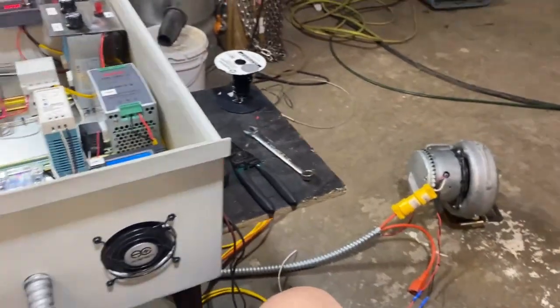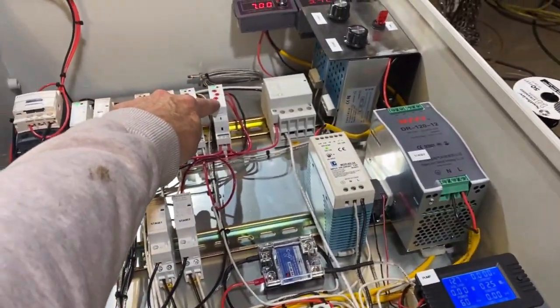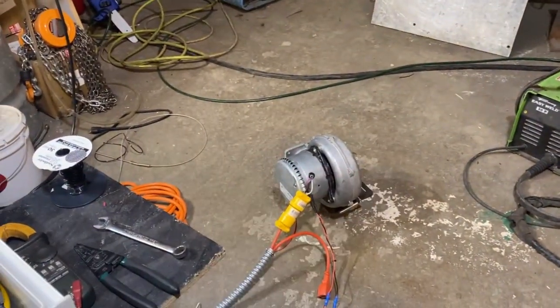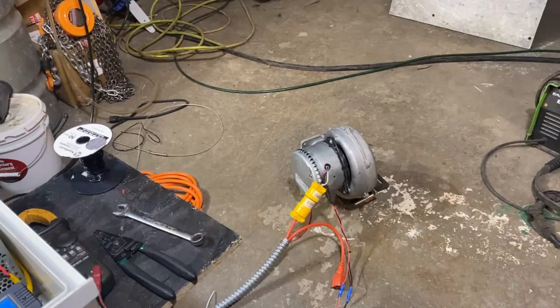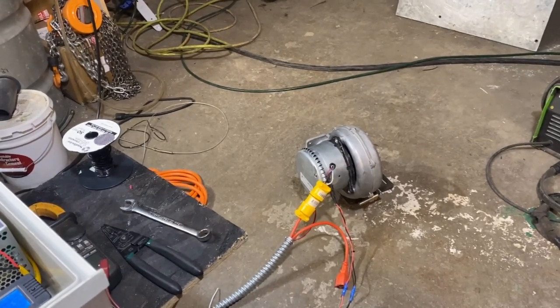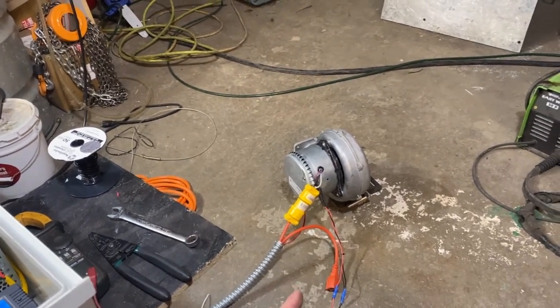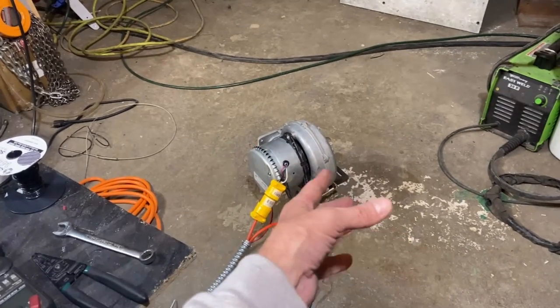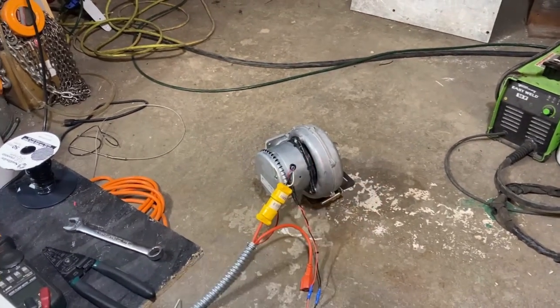So let's take a look, and then once that happens when I go to turn this off we're going to want to see this blower timer relay kick on and run the blower on shutdown mode to cool off the combustion chamber and to blow out any residual fuel and to stop residual heat from coming back up into the blower and damaging it.